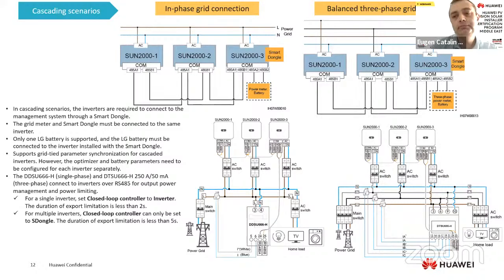I need to add here something because some of the customers are confused. You cannot monitor the slave inverter in the master inverter by going to device management and selecting the slave. The inverter does not have this capability. The master inverter will send all the data to Fusion Solar. So only in the Fusion Solar app or web can you see all the inverters there.